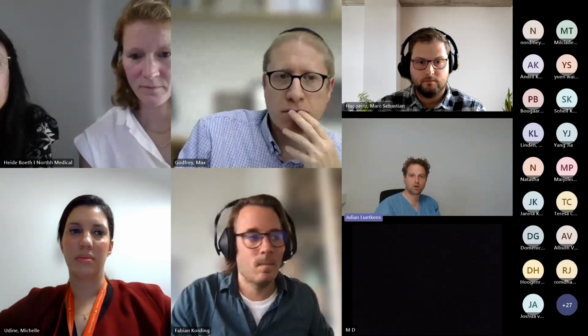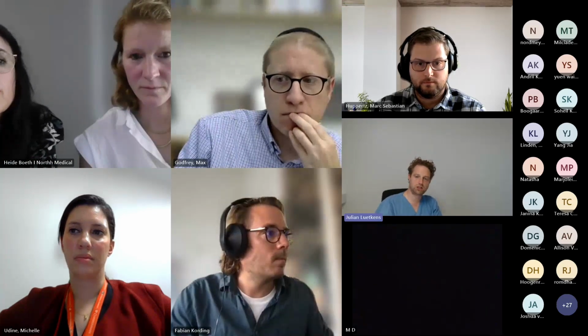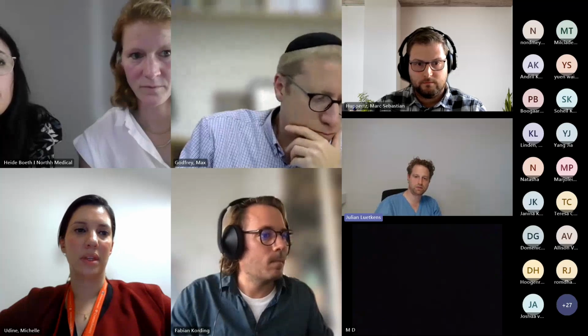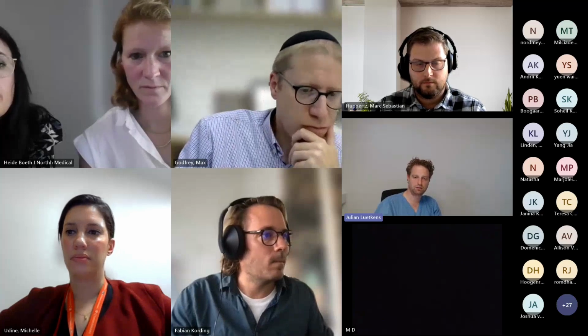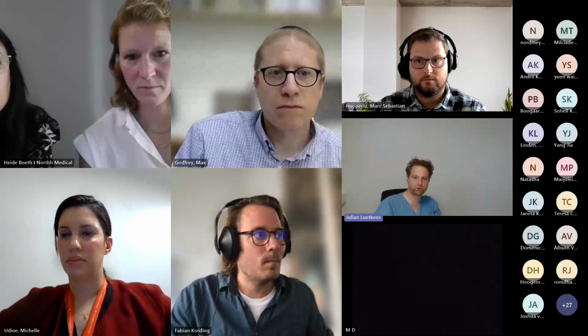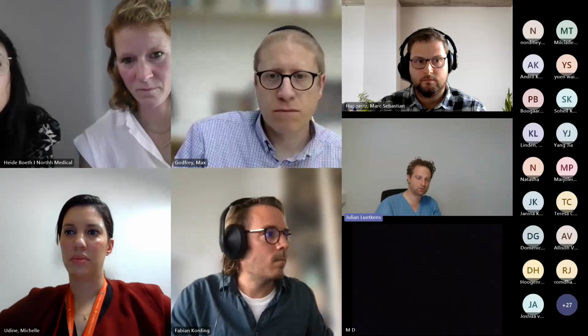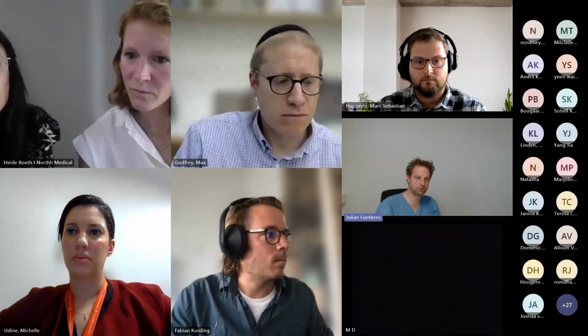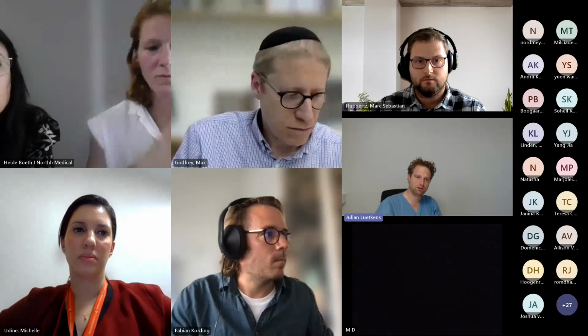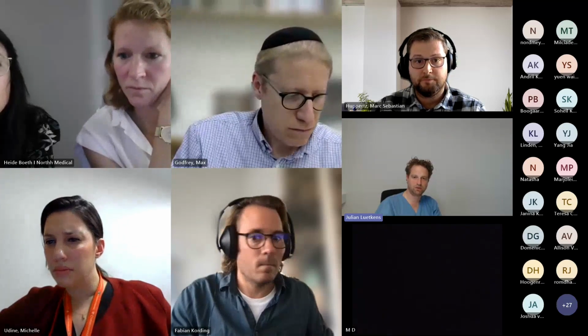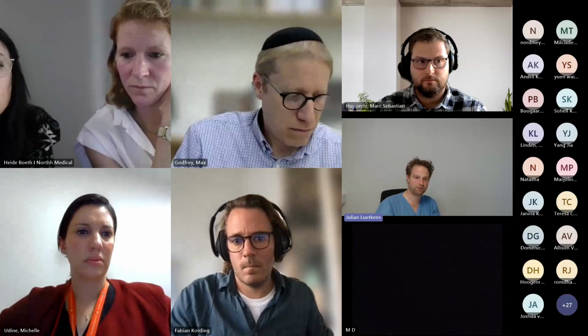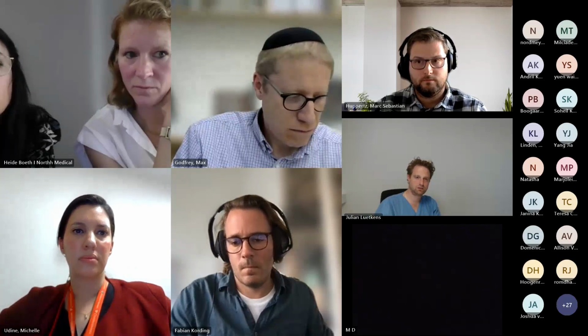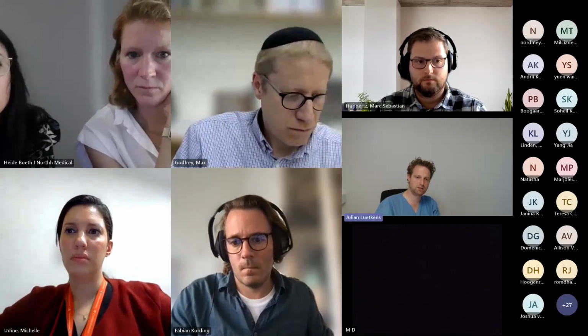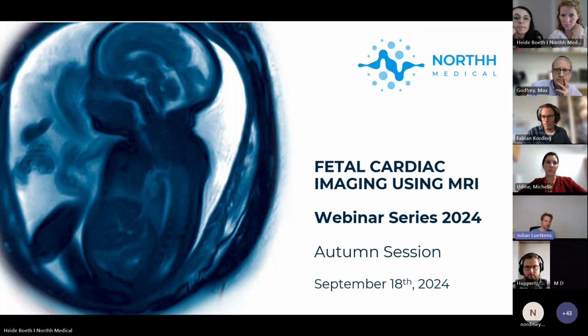Maybe another comment to this is what Joshua just said. Regarding the field strength, I think you can do good images on 1.5 Tesla as well. But if you look for specific sequences, like for example 4D flow, I think there you have a great advantage with higher field strength. So this is at least my experience, that you have a gain in SNR there.